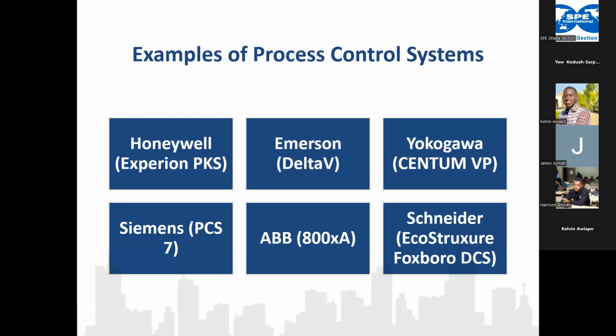These are examples of process control systems that we have, or DCS systems. And these vendors like Honeywell, Yokogawa, Emerson, and Siemens also, are also into PLC manufacturing. So it's basically the same. They run through SCADA PLCs as well as the DCS. The DCS is usually vendor specific, so it's a bit difficult to add other systems to it unless you get some specialized skill or maybe the vendor to help you in that.